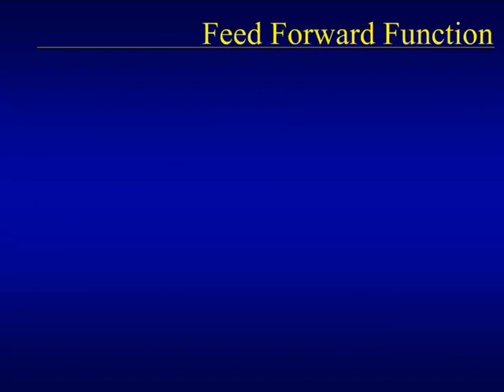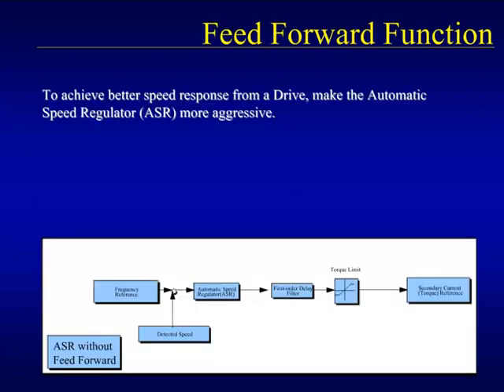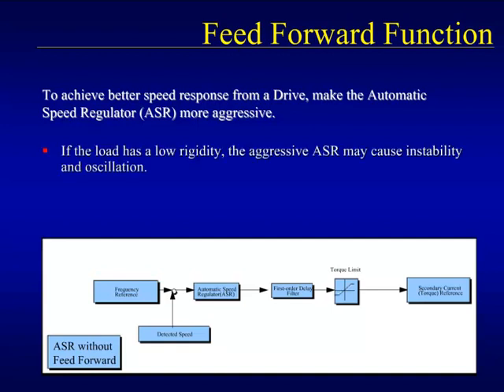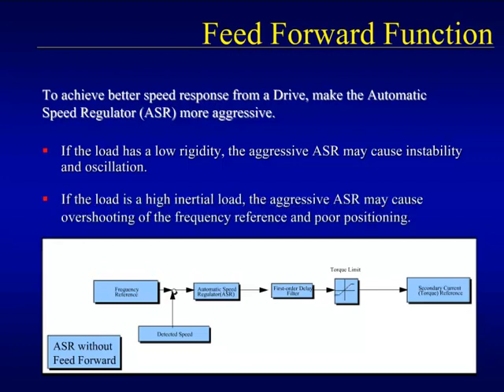The automatic speed regulator, or ASR circuitry, is a PI circuit that regulates the drive output to achieve accurate speed regulation. In order to achieve tighter speed regulation, more aggressive ASR settings are required. If there is some play in the load, an aggressive ASR might cause oscillation in the output speed because the ASR will keep changing as it chases the inconsistent load. If the load has a large inertia, then an aggressive ASR will cause vibration and the drive's output frequency will probably overshoot the intended speed.